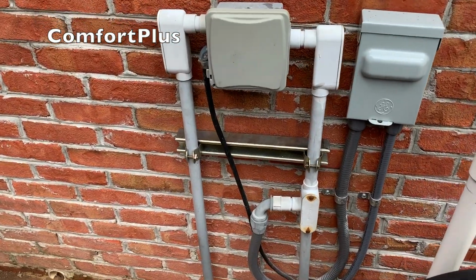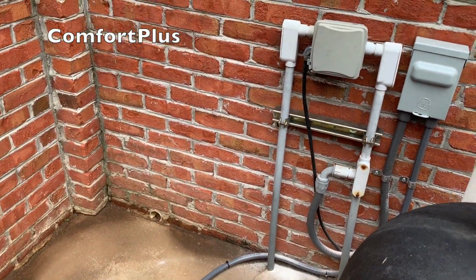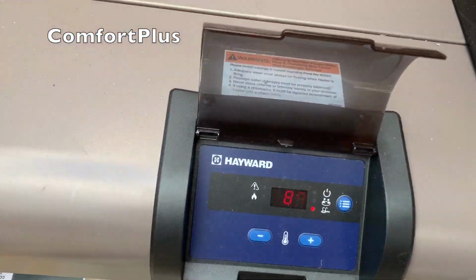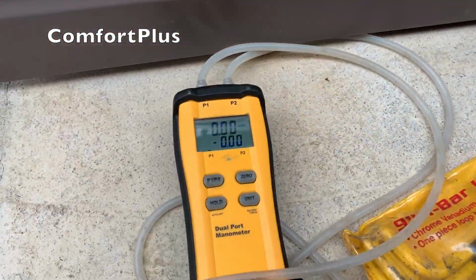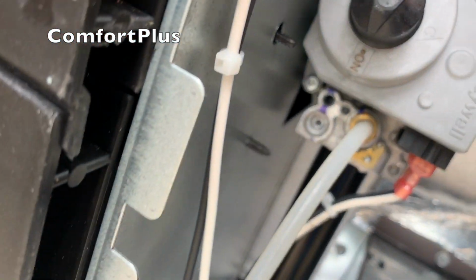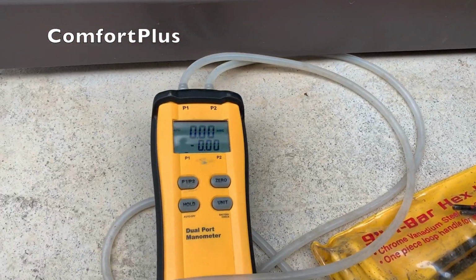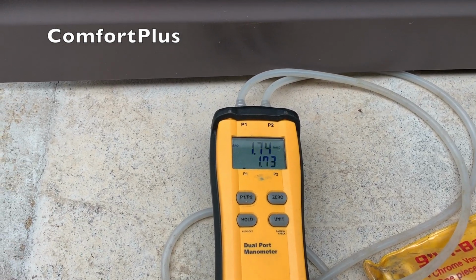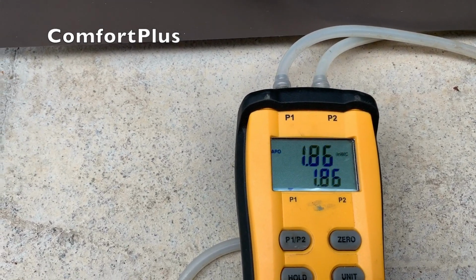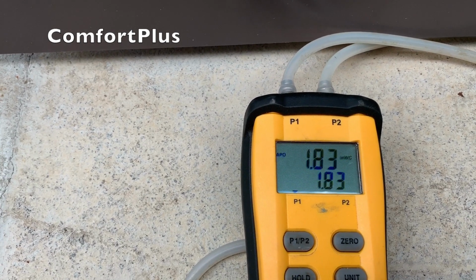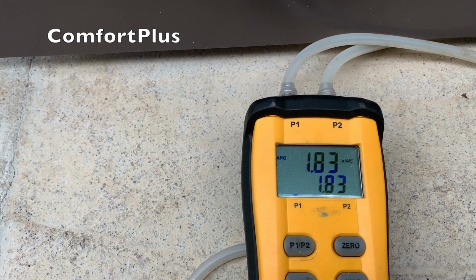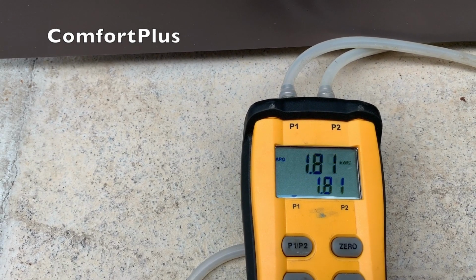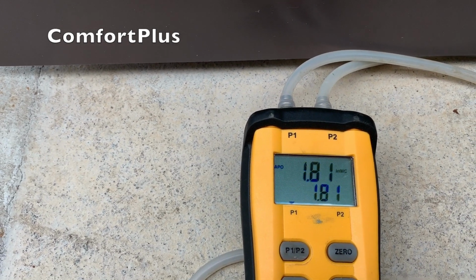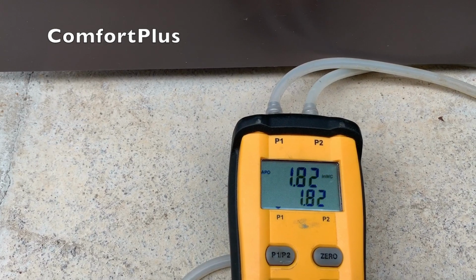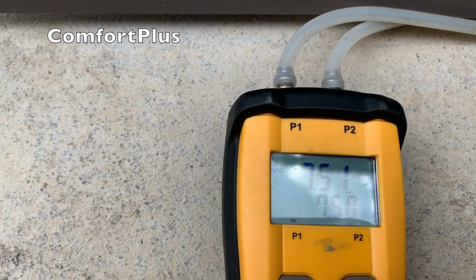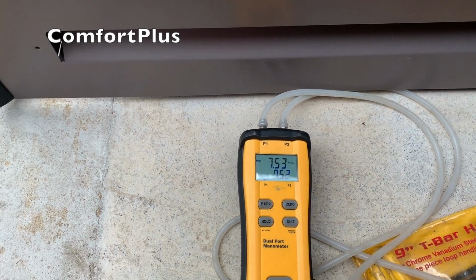Okay, next day, as promised, got that strapped to the wall with some unistrut. Waiting for this thing to come on so we can test the gas pressure. I'm testing it on the manifold side right now. They want 1.8 to 2.0. 1.83, so that's more than 1.8. I'm going to check the inlet side just to make sure how much we're getting over here. About 7.5, so we're all within spec.